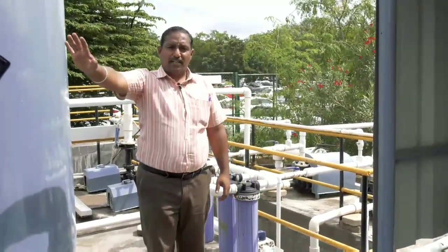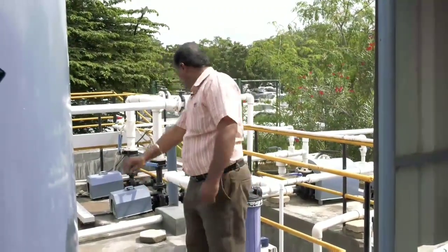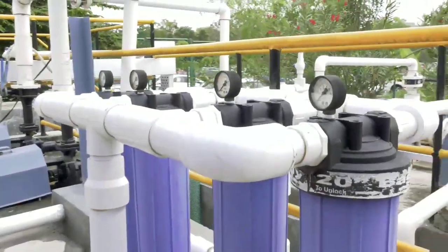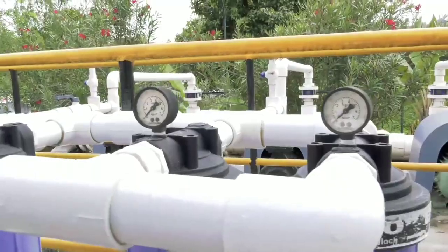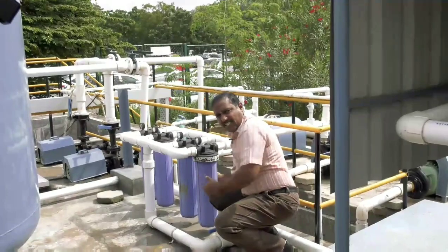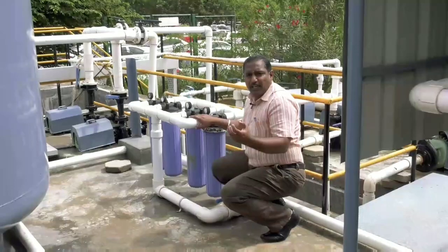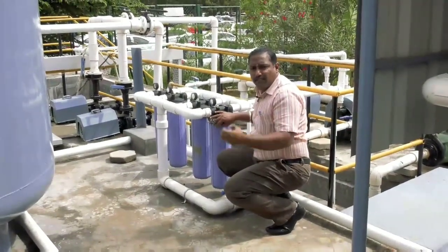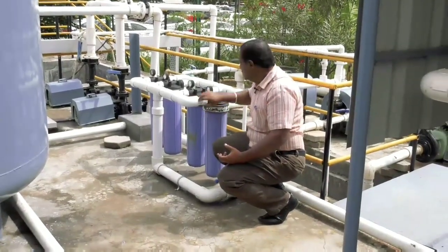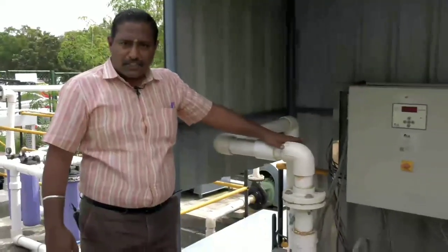After this activated carbon filtration, the treated sewage or treated wastewater enters the bag filter. You can see the units over here. There are 4 units, which are bag filters. Cloth bags of 5 micron size are present inside this cylinder. Even the very fine suspended impurities are removed over here, because the size is very small, 5 micron. Then the sewage is passed to the final stage of treatment, the disinfection part.